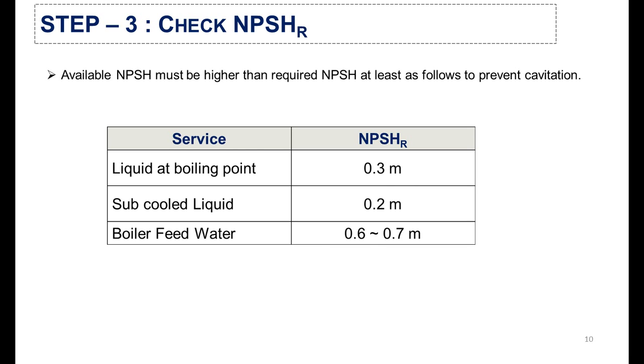In the third step, you will check the net positive suction head required (NPSHr). It is important that the available NPSHa must be higher than the required NPSHr. In this table, typical values of NPSHr are given: for liquid at boiling point it is 0.3 m, for subcooled liquid it is 0.2 m, and for boiler feed water it is 0.6 to 0.7 m.